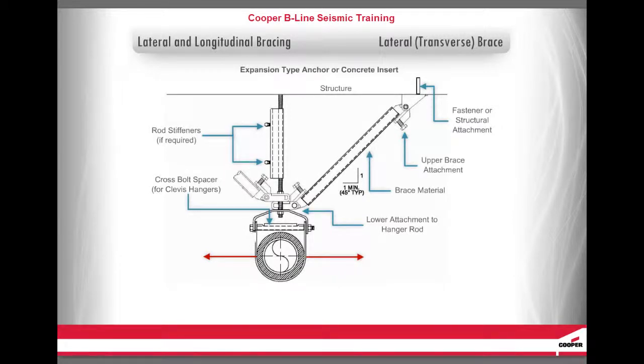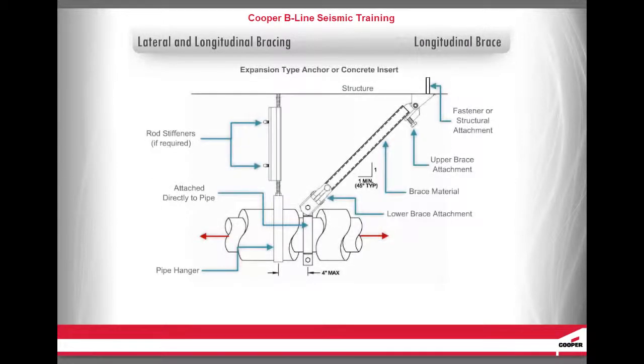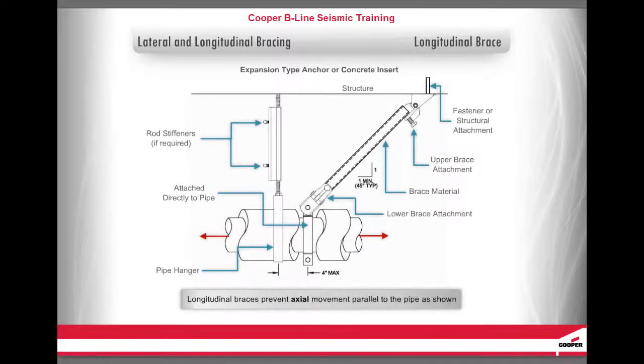Here is a diagram of a lateral or transverse brace. Lateral transverse braces prevent movement perpendicular to the pipe, for cable tray, air duct, conduit, or other non-structural systems. Here is a diagram of a longitudinal brace. Longitudinal braces prevent axial movement parallel to the pipe, for cable tray, air duct, conduit, or other non-structural systems.